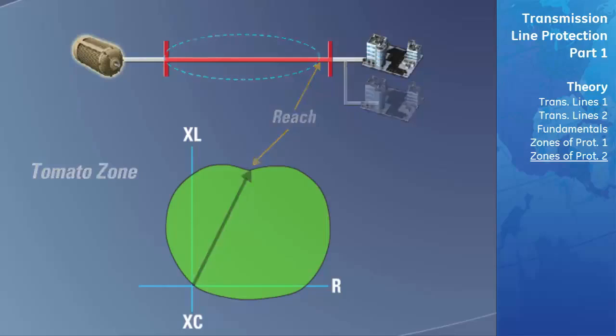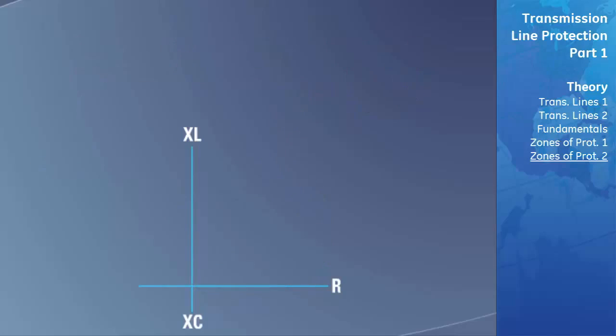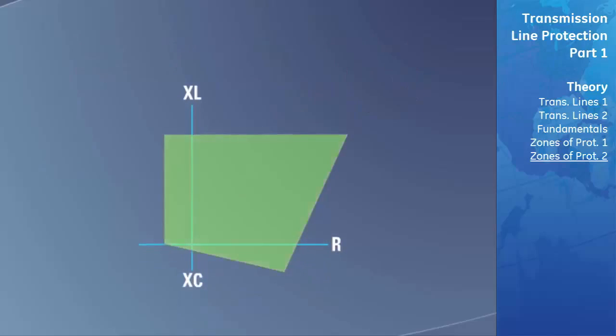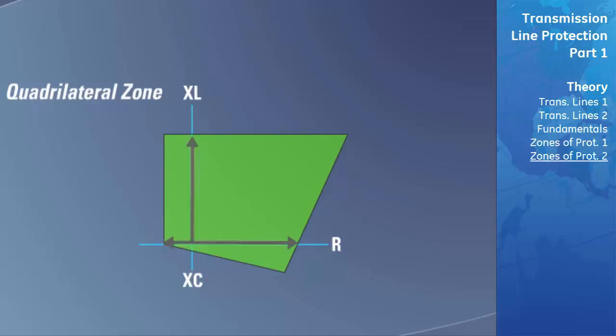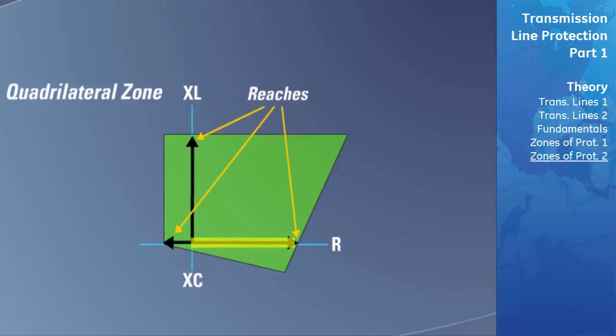Another custom zone is known as a quadrilateral zone of protection. This type of zone allows you to set the reactance and resistive upper and lower boundaries to create your own custom shape to match the needs of your power system. In this type of zone, there are essentially two reaches: one in the inductive direction and one in the resistive direction.